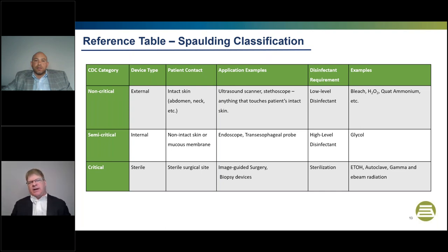Next comes the semi-critical category, and this is going to be an internal device type that gets in touch with non-intact skin or a mucous membrane. That could be even a laryngoscope, endoscope, transesophageal probe in cardiac ultrasound, and requires a high-level disinfectant. And anyone who's ever had the unique joy of a colonoscopy would be happy to know that the scope bathed in a glycol bath overnight. This is not meant to be an exhaustive list of all the chemicals and devices - this is just an example to try to put it in a nice table here.